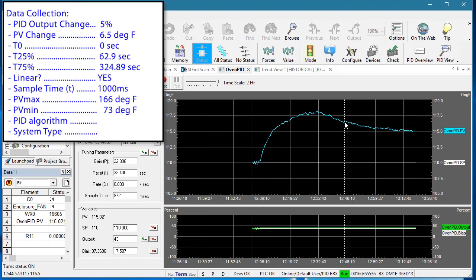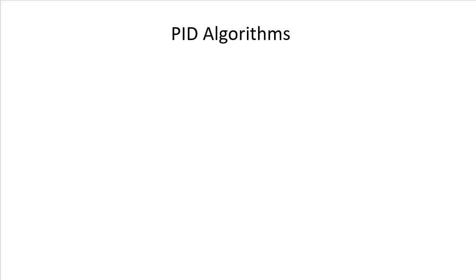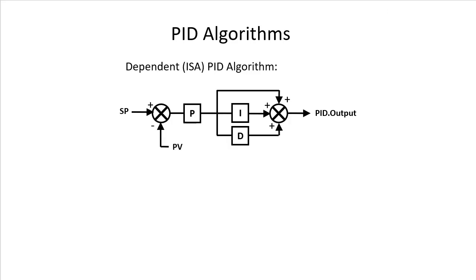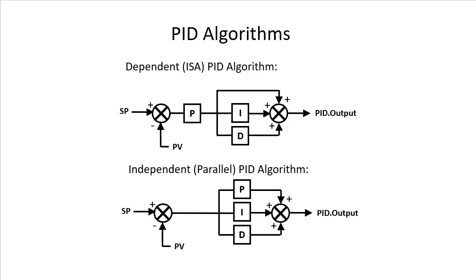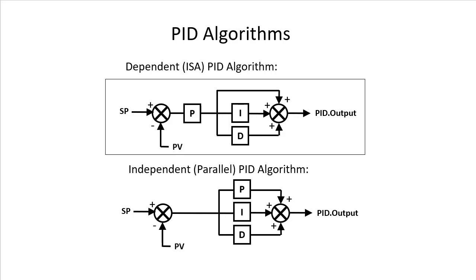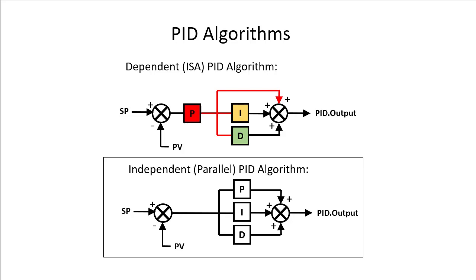We also need to know which PID algorithm we have. The two most common ones are the dependent or ISA version and the independent or parallel version. In this one, the I and the D coefficients depend on the value of P. Every time you change P, you have to adjust I and D. In the independent version, you can adjust each coefficient independently because they don't affect each other. Each coefficient just contributes to the overall result.